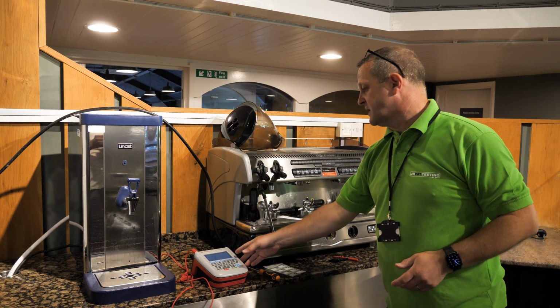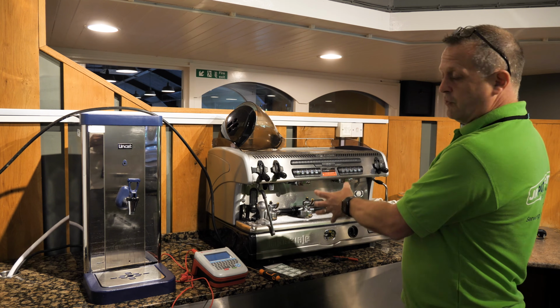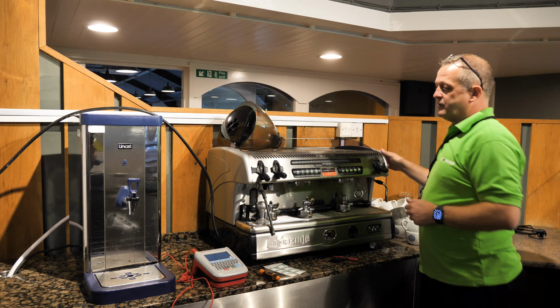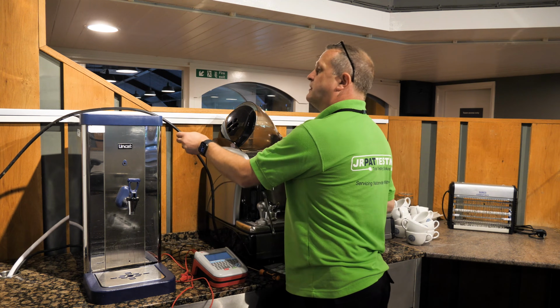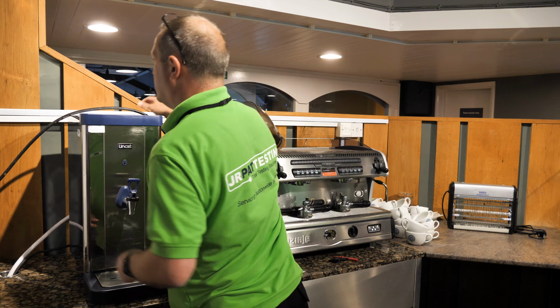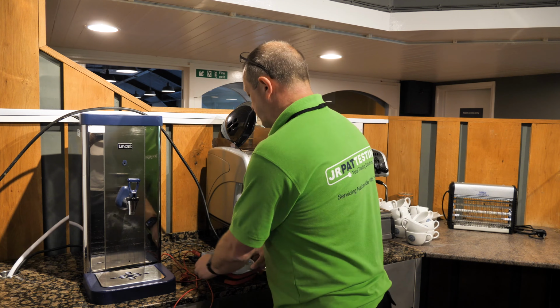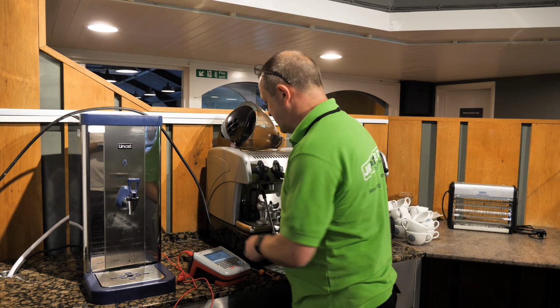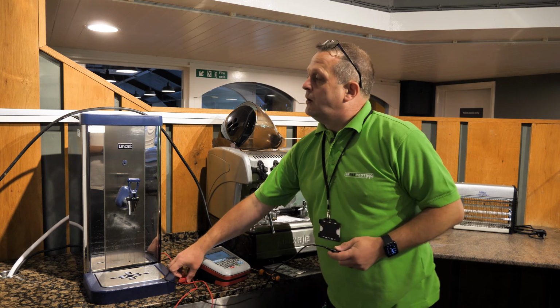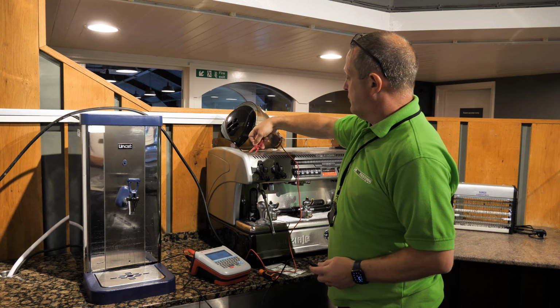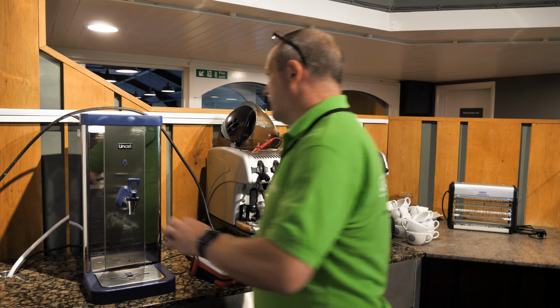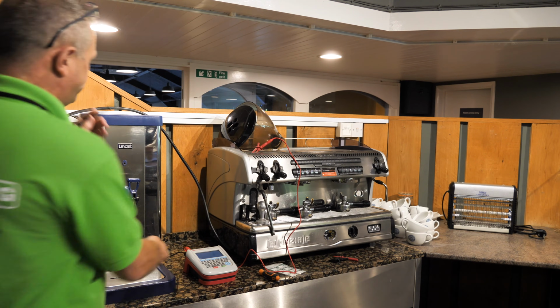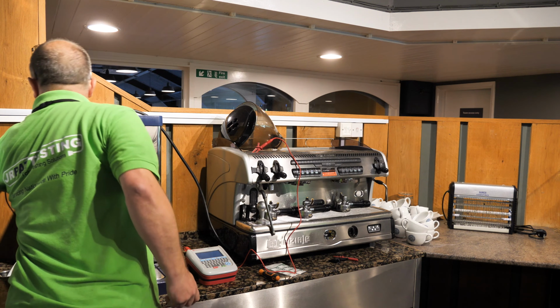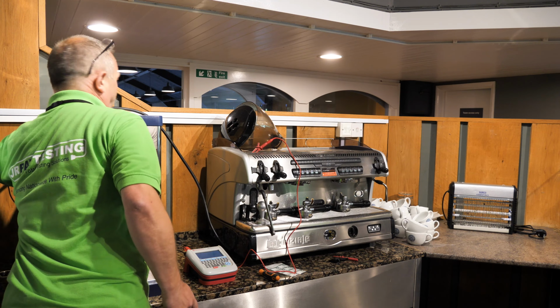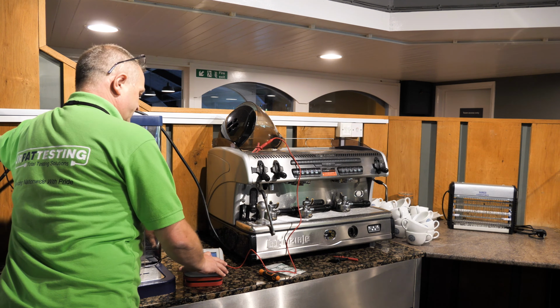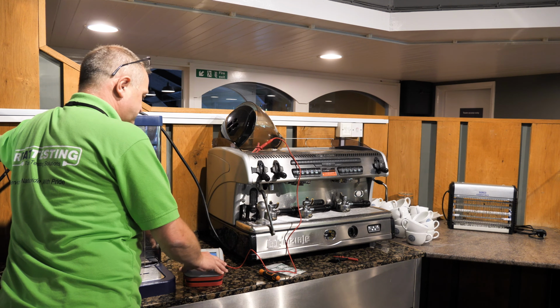So I'm going to select a class 1 appliance test, fixed appliance test, and conduct the visual inspection. Again, just looking around, making sure that everything appears okay, checking the sheath on the cable and making sure that's all in order. So I'm happy with the visual inspection. I'm going to select a fixed appliance test, and attach a crocodile clip to exposed metal parts, and then using the other probe, attach that to the screw on the spur switch in order to conduct an earth continuity test.